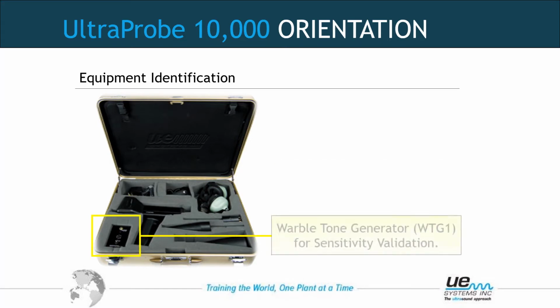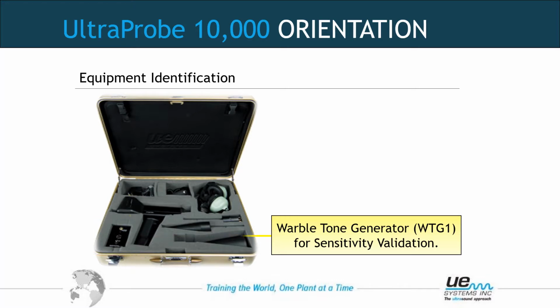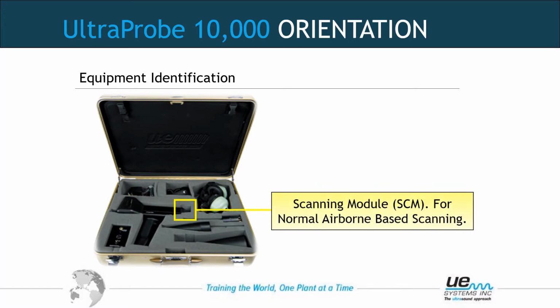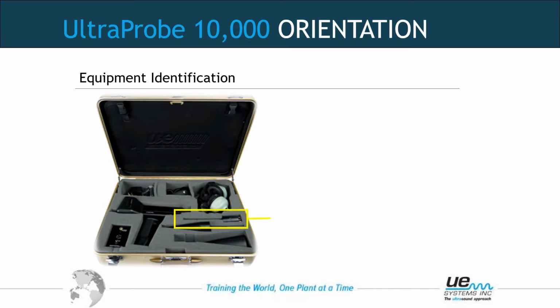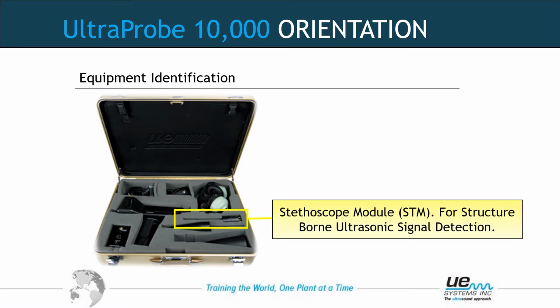The warble tone generator that emits a false ultrasonic sound with a rechargeable battery used for sensitivity validation. The scanning module, which has a 60-degree field of view and is used for normal scanning distances, attached to the Ultraprobe when first shipped. The stethoscope module used for structure-borne inspections. It is a wave guide to guide the sound out of the structure to the piezoelectric crystals in the module.